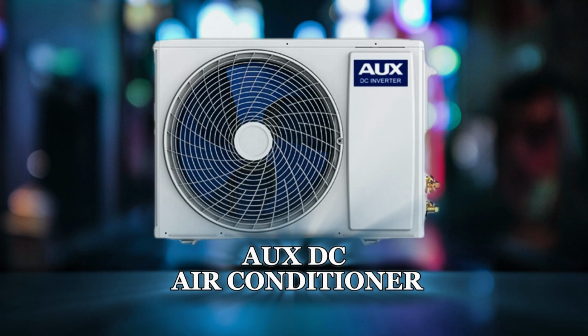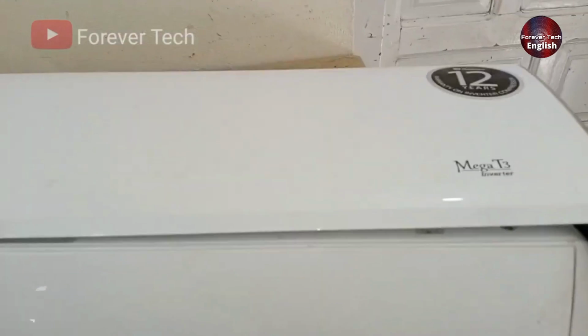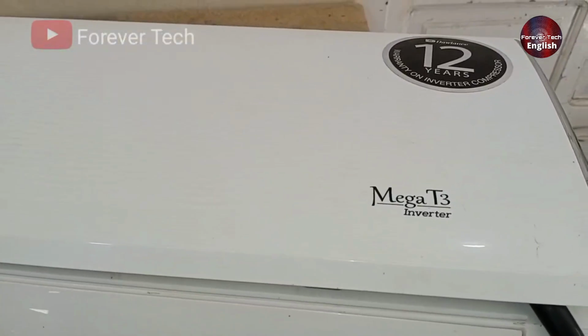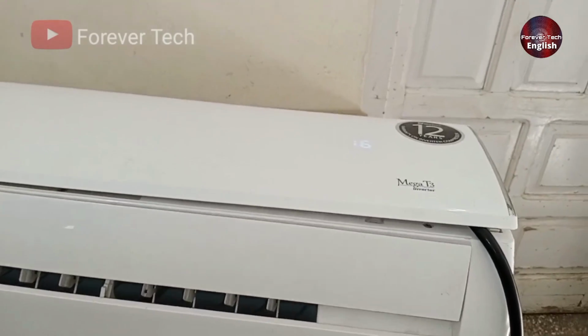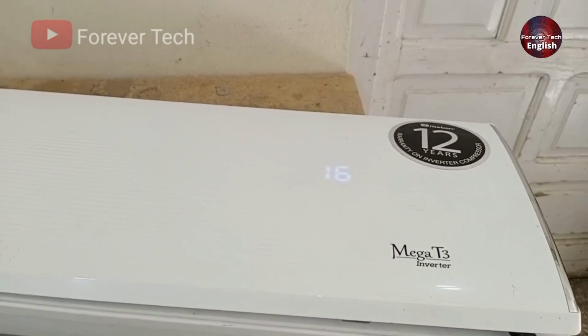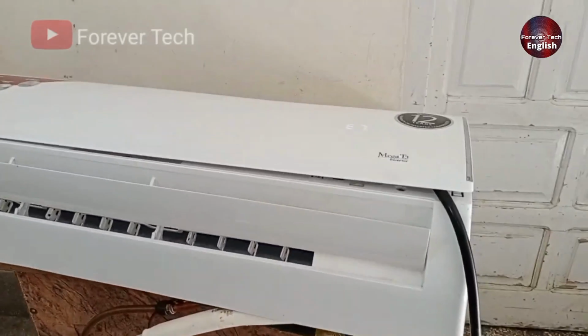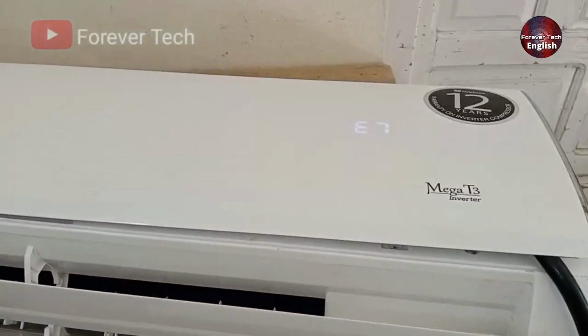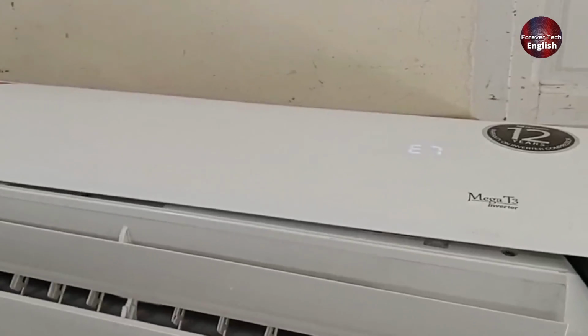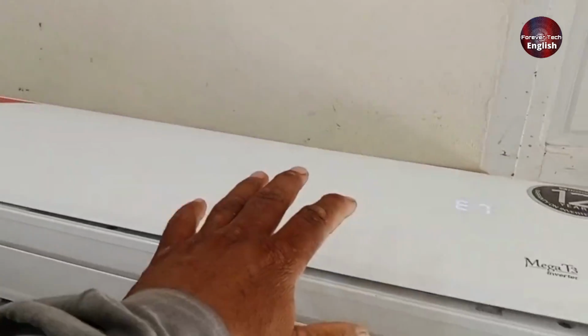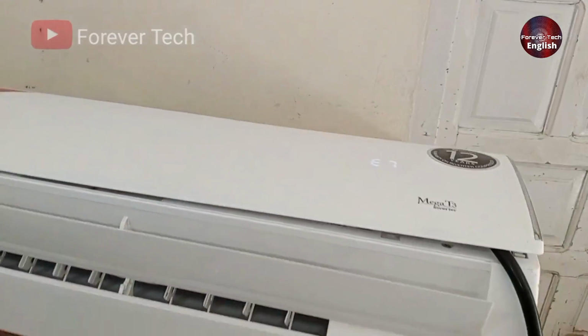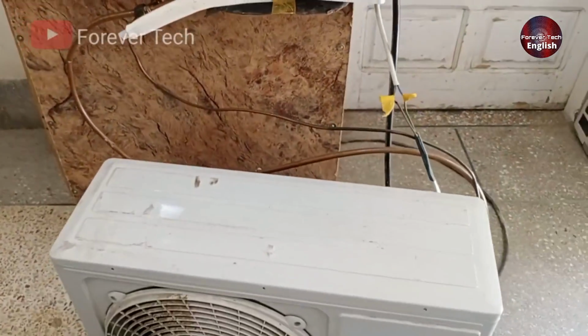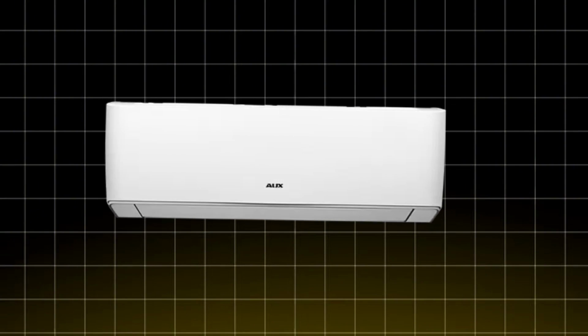I have an Aux DC inverter air conditioner, specifically the Mega T3 inverter model, and it's showing an error. I've started the unit and set it to 16 degrees, so let's see what error it shows. As you can see, the indoor unit's display is showing an E7 error code. This means that when E7 appears, the indoor unit is working very well and blowing air effectively, but the outdoor unit has completely stopped. So, the fault is not with the indoor unit, but with the outdoor unit.